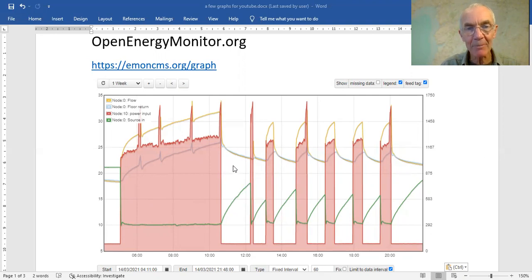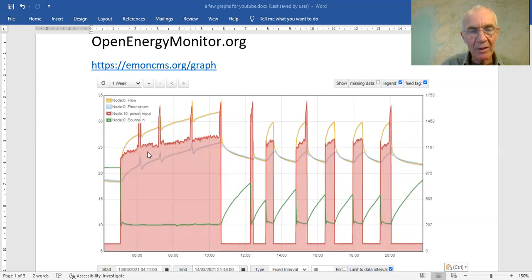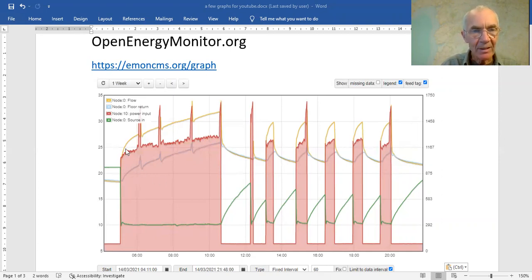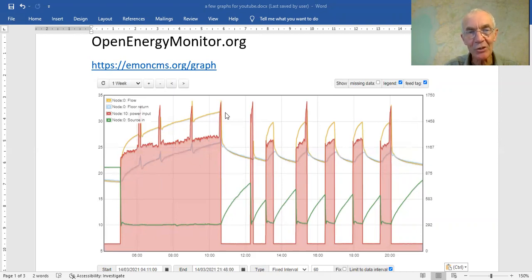This is a fixed speed, fairly old ground source heat pump — in fact it's a spring source heat pump because it's a very nice high temperature source. Looking at the graph: the input power is about 1.2 kilowatts. These two lines are the flow temperature and the return temperature, and I think it's very important to have both. If you're just looking at the flow temperature, you don't have much confidence that anything is actually flowing in that pipe.